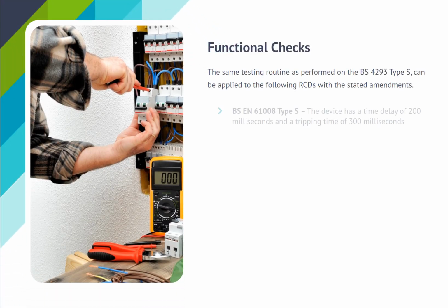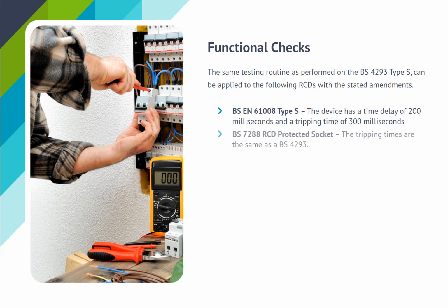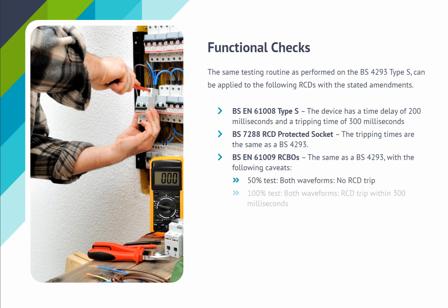The same testing routine as performed on the BS4293 Type S can be applied to the following RCDs with the stated amendments. BS EN 61008 Type S: the device has a time delay of 200 milliseconds and a tripping time of 300 milliseconds. BS7288 RCD protected socket: the tripping times are the same as a BS4293.